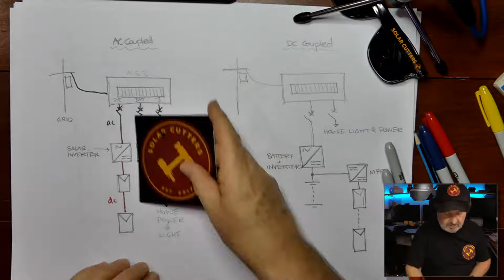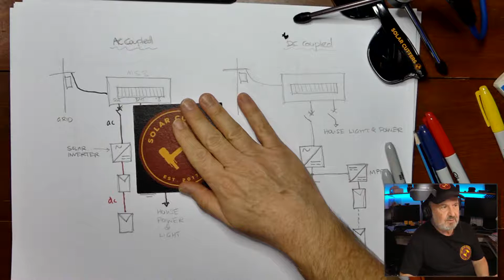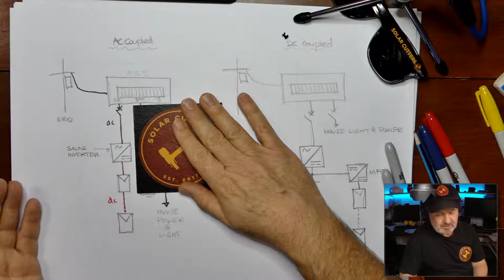What that means is you could start off with just a solar inverter supplying clean renewable energy to your home, and it works fine. If you want to add storage, you can add in parallel an AC coupled battery inverter. But now you've got two inverters, each with AC ratings—say 5 kilowatts each—meaning you have 10 kilowatts of inverter power in parallel connected to the utility grid, because they're feeding the same connection point.